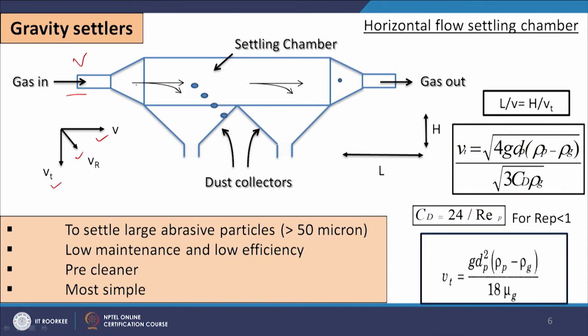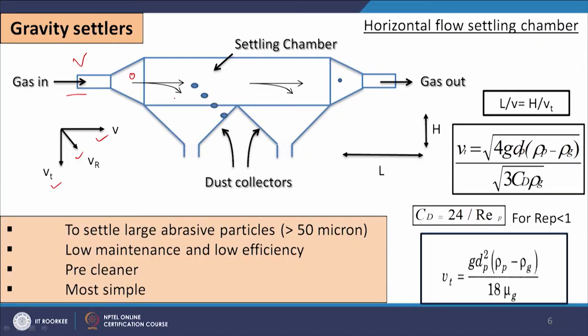If we consider one particle, the basic principle of separation is: if we can put something in its path, its flow will be arrested and the velocity in that direction becomes zero, so the particle will fall. For this particle to settle, the time required to travel from inlet to outlet must be sufficient for the particle to travel the full vertical distance equal to the height of the settling chamber. This is the basic requirement or design principle for this settling chamber.